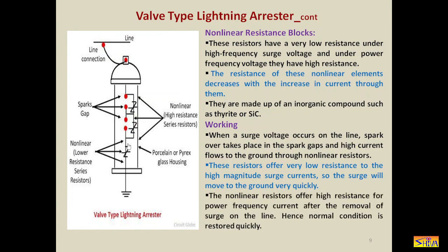The nonlinear resistors offer high resistance for power frequency current after the removal of surge on the line. Hence, normal condition is restored quickly. So when high frequency discharge current stops, these resistors offer high resistance to power frequency follow-up current. Therefore, normal conditions are restored quickly.